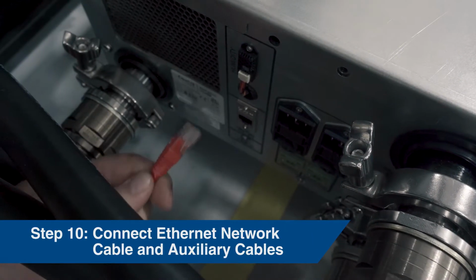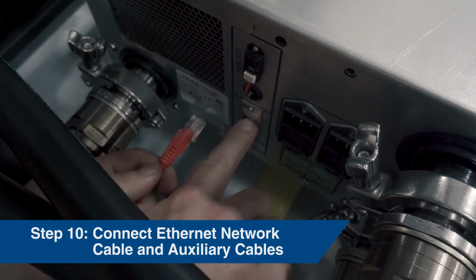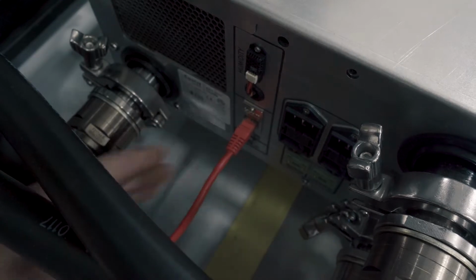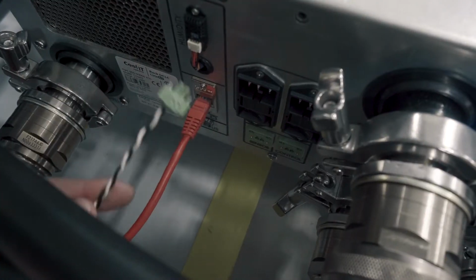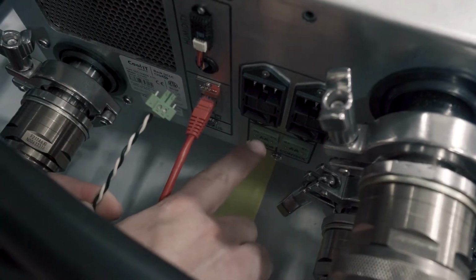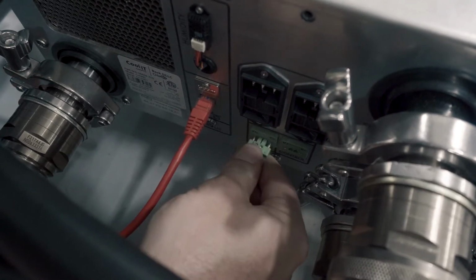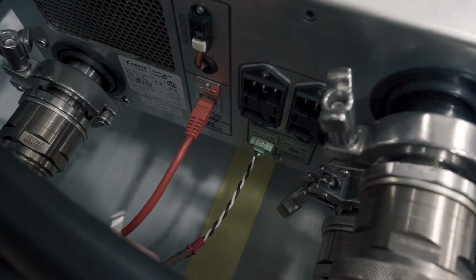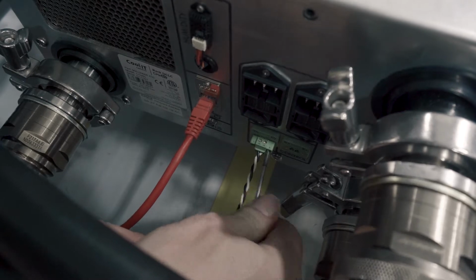Step 10. Connect Ethernet network cable and auxiliary cables. Connect all required Ethernet network cables and auxiliary cables to the heat exchanger. This next step may involve your IT group to provide the necessary connections from the network.